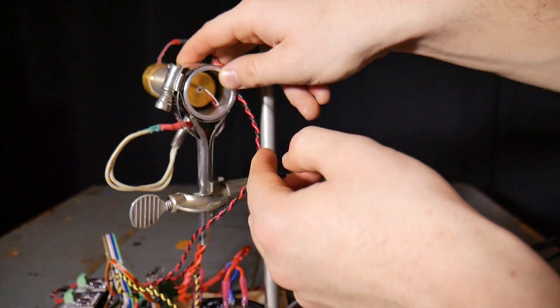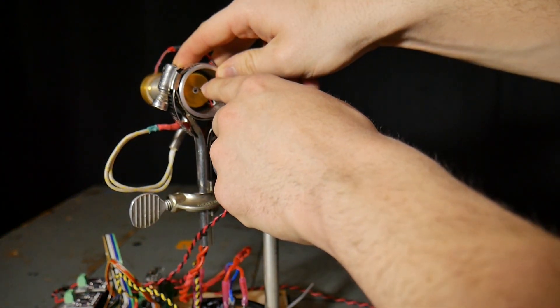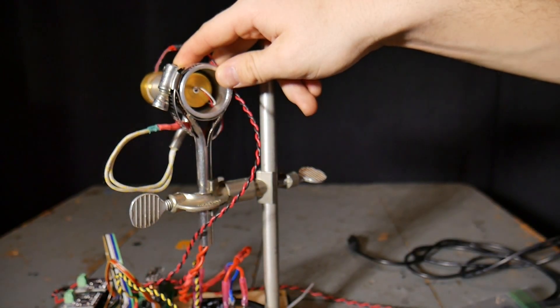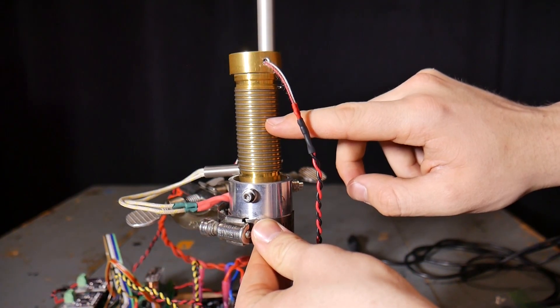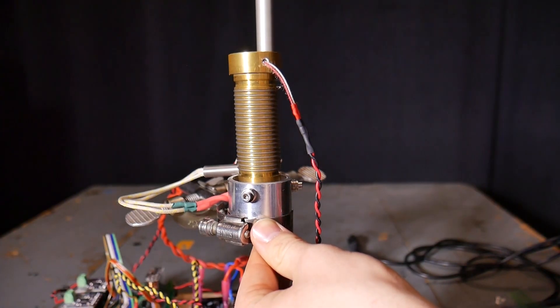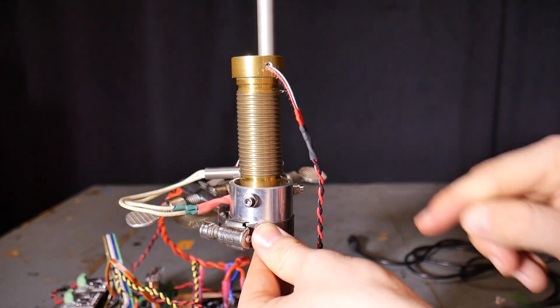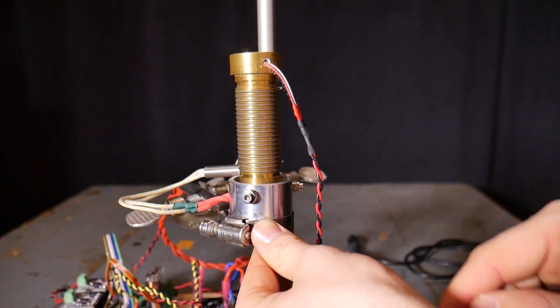If I lift this up, you can see that the heating element has another hole drilled in the bottom where a third thermal probe is inserted. This is inserted all the way to around the middle of the heating element, such that it has a very quick response time to changes in the state of the heater.